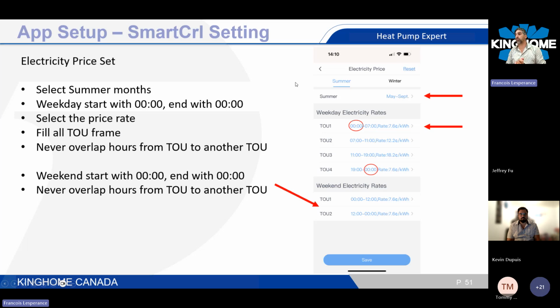So there are some rules that you have to know before you set up this menu. First things first, we're gonna select the summer period. You can select the summer period, like in this example, May to September. Now, on a weekday, we have 4 different times of use. The most important thing to know is to start with 00 and it must end with 00. And you cannot overlap hours.